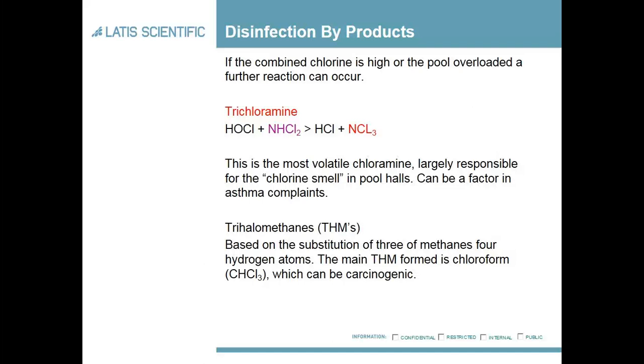Trichloramine is the most volatile of the chloramines and is largely responsible for the chlorine smell in pools. It's not that there's too much chlorine in the water — it's that there's actually too much contamination in the water, and that's coming out of solution and that's what you can smell. This can be an asthma trigger, so you will often get people with asthma complaining about their breathing in these pool areas. Trihalomethanes are also a major byproduct. These are based on substitution of the free hydrogen ions in methane, and the main THM formed is chloroform, which is carcinogenic, which is why you want the levels to be as low as possible.